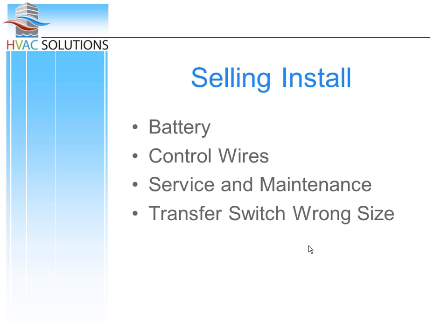I always bring up transfer switch sizing because we size transfer switches for the power delivered to the house. So if you have a 200 amp service to the house, you're going to go with a 200 amp transfer switch. What happens if you sell a 100 amp transfer switch and they have 200 amp coming to the house? Well, it may work, but you just cut down the amp rating to the house - you took it from 200 down to 100. I've actually seen those work, but it blows my mind.